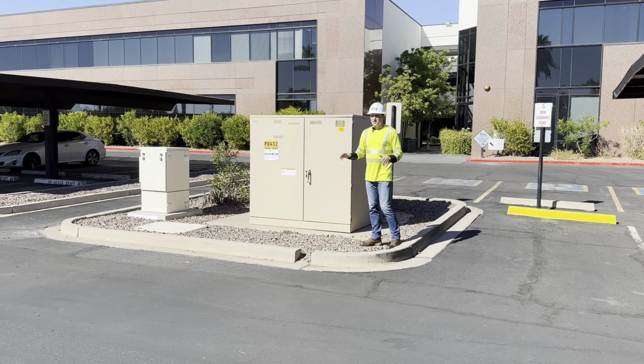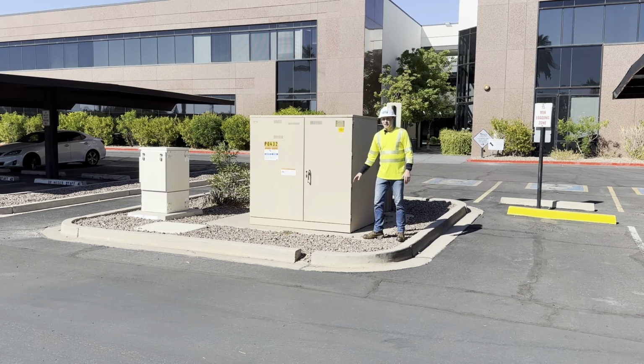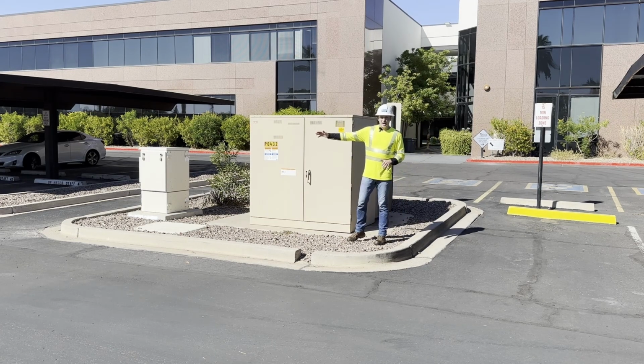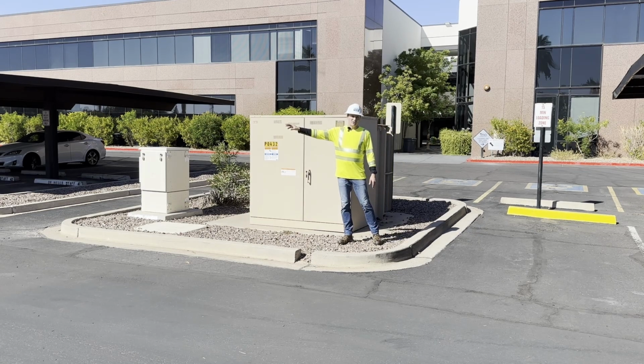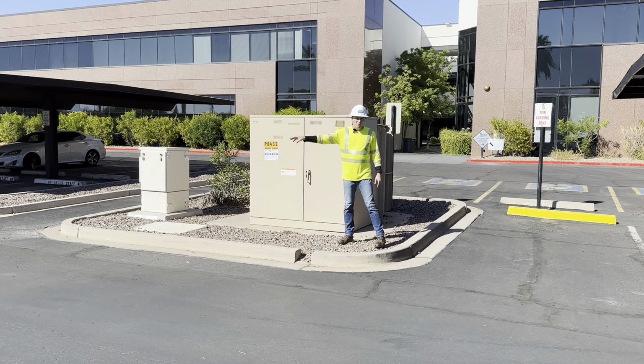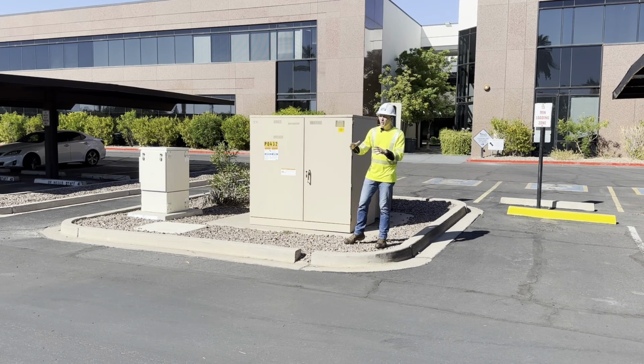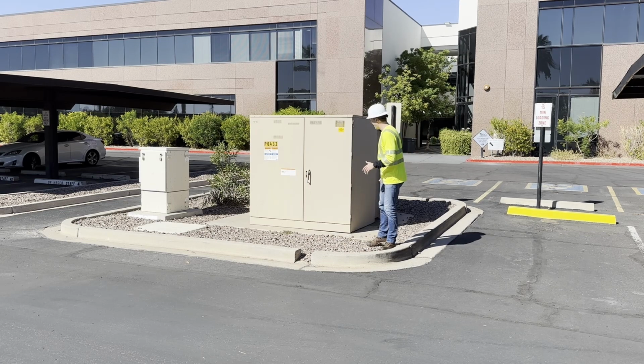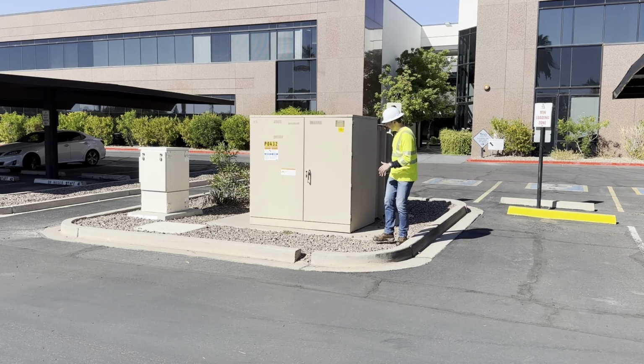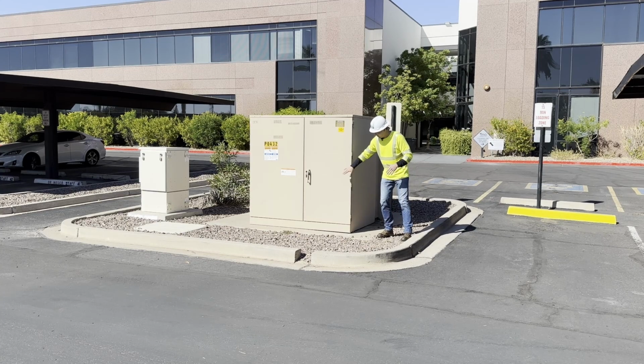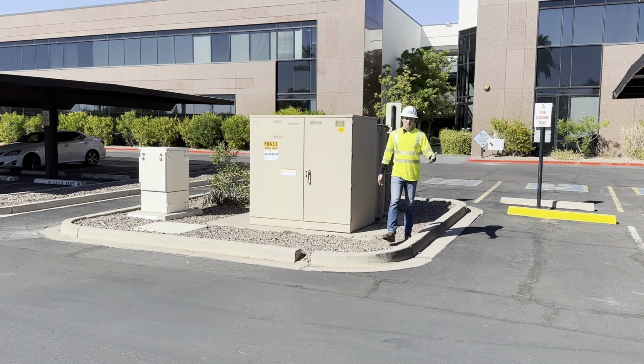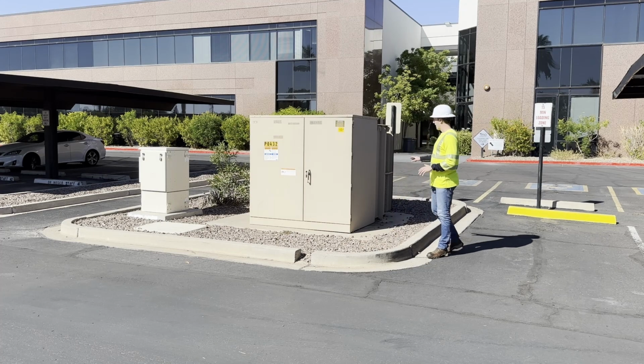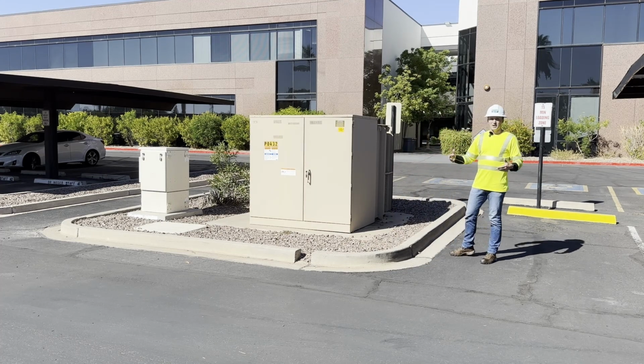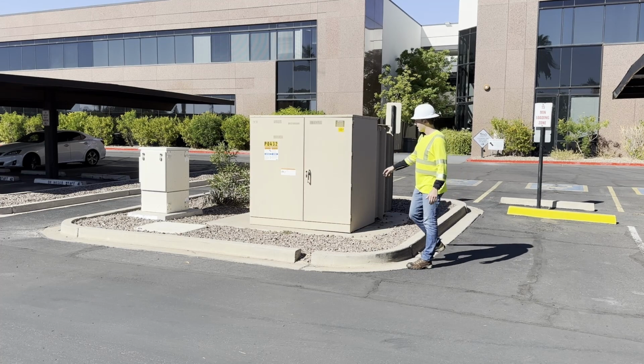the customer side responsibility is putting this pad in an area that's agreeable to the utility. Also, sweeping out primary conduits to wherever the utility is going to be intercepting them. Sometimes that goes to a primary pole box. Sometimes that goes to the bell hole of a switch. It can be different locations depending on what the utility wants. And then on the secondary side, you have to sweep out those conduits as well, going out to wherever your switchgear is going to be located. So it's really important that you put this transformer in an area that makes the most sense for both you and the utility.